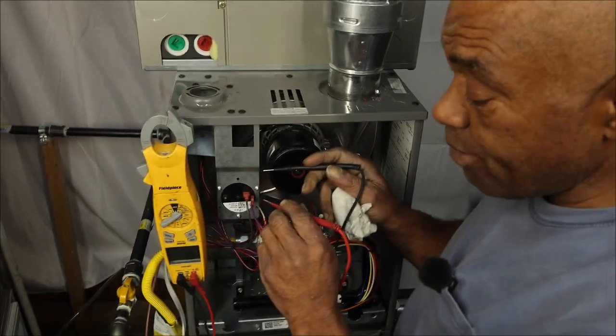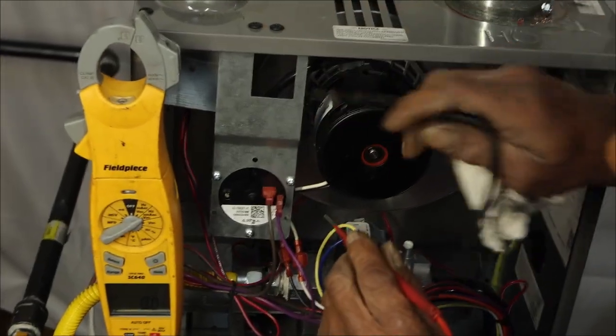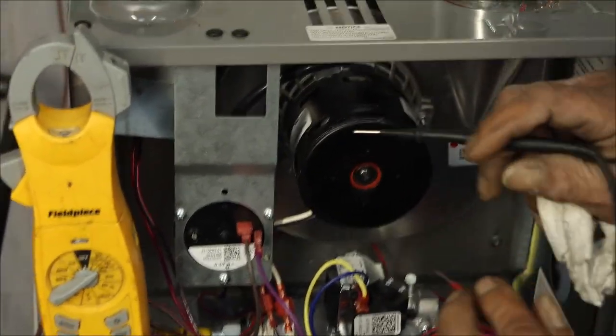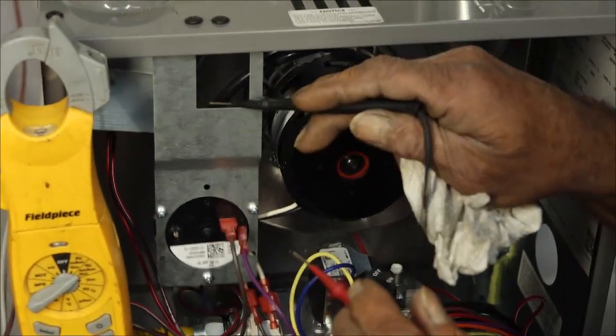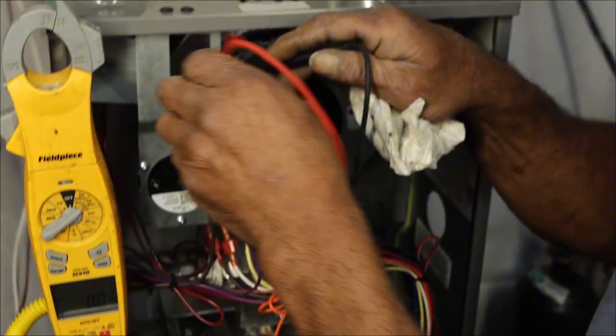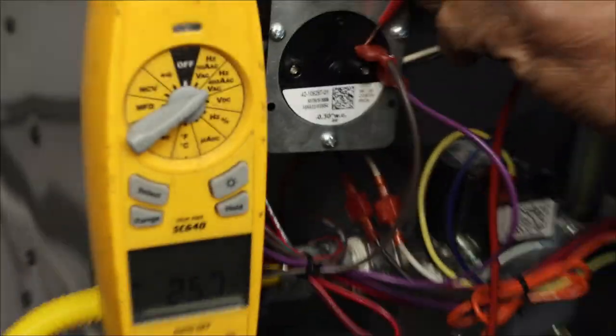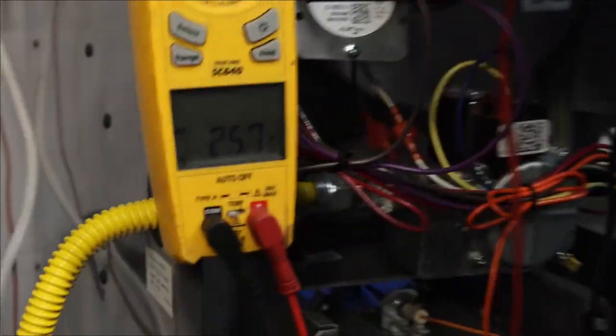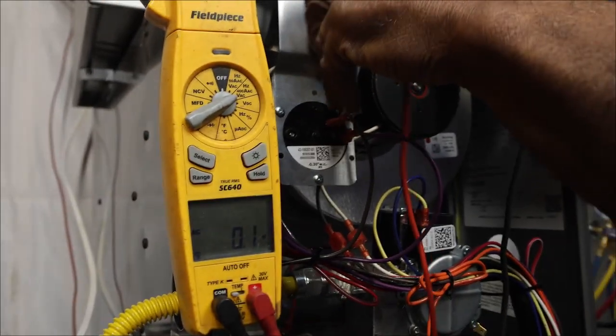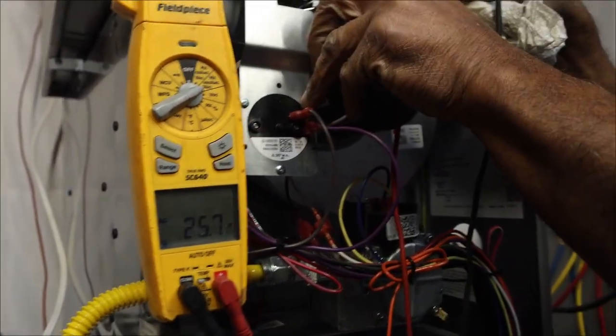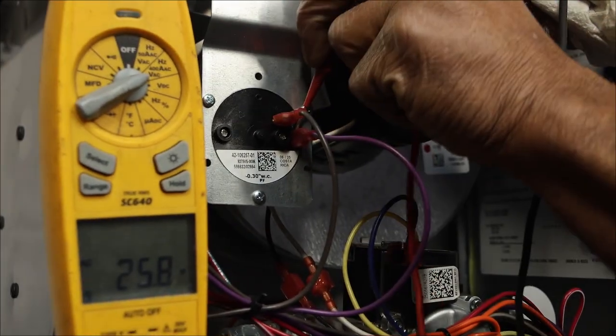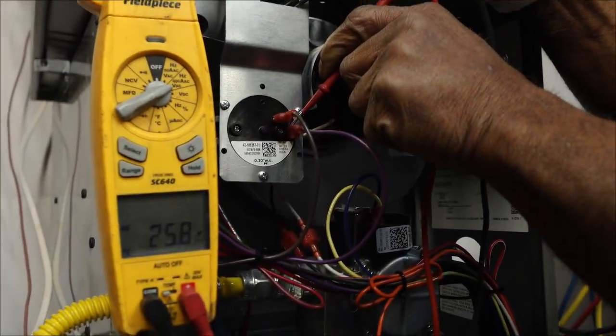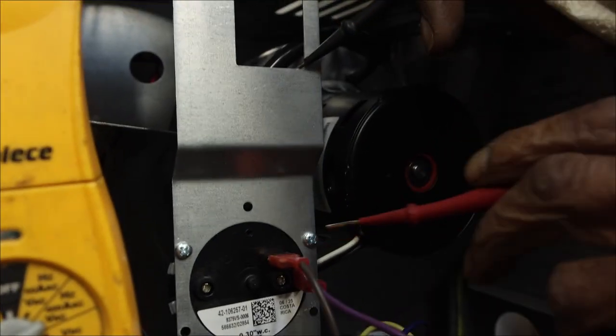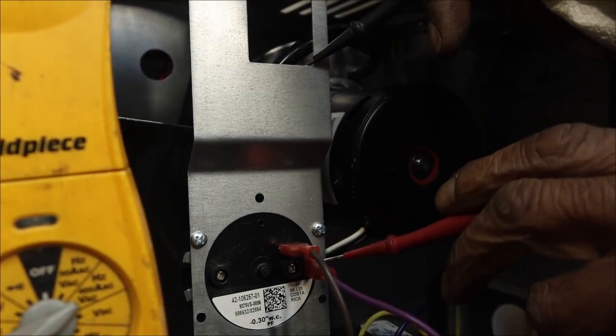I can use my amp probe by grounding to the side of the unit. I touch that flue, she's a little warm. I can ground to the side of the unit, and then I can check to verify that I got power coming in. Looking at my amp probe, I got 26 volts. Then, if I check the lead going out, I see that I still have 25 volts, but my ground is just grounded to the unit because this is power in and that same power out.